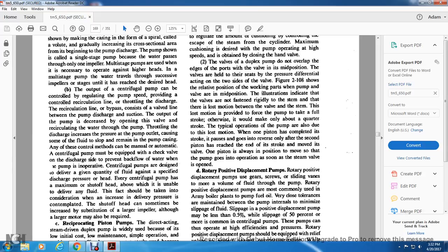Any of the control methods can be manual or automatic. Centrifugal pumps must be coupled with a check valve on the discharge side to prevent backflow of the water when one pump is inoperative.